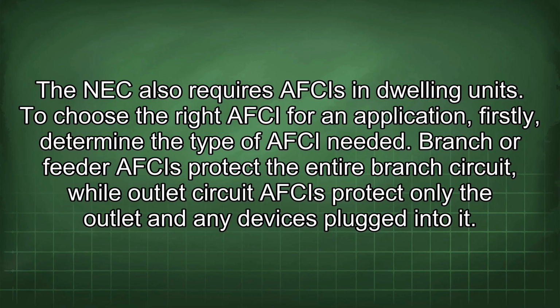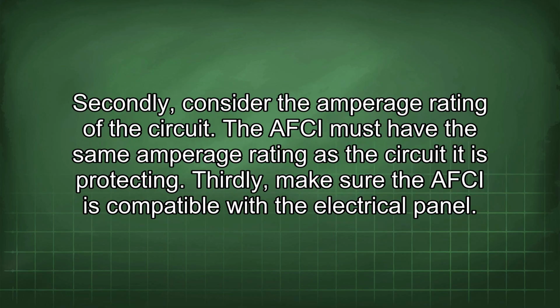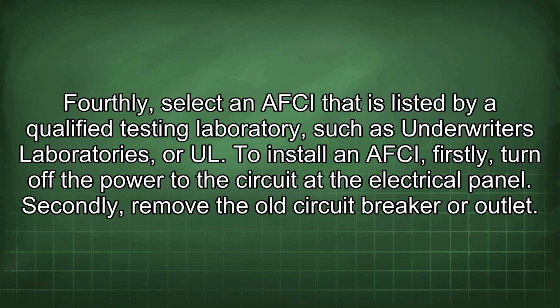To choose the right AFCI for an application, firstly determine the type of AFCI needed. Branch or feeder AFCIs protect the entire branch circuit, while outlet circuit AFCIs protect only the outlet and any devices plugged into it. Secondly, consider the amperage rating of the circuit. The AFCI must have the same amperage rating as the circuit it is protecting. Thirdly, make sure the AFCI is compatible with the electrical panel. Fourthly, select an AFCI that is listed by a qualified testing laboratory, such as Underwriters Laboratories or UL.